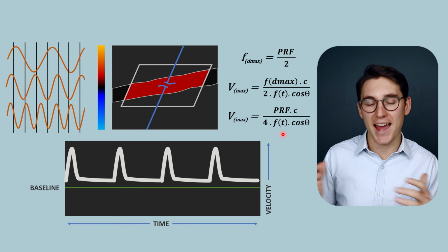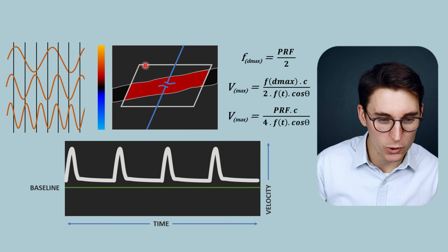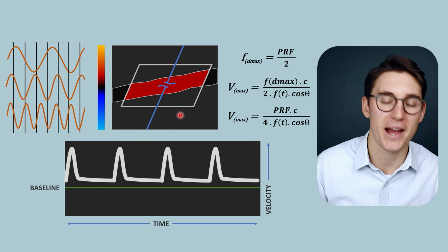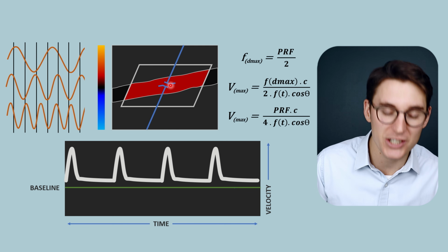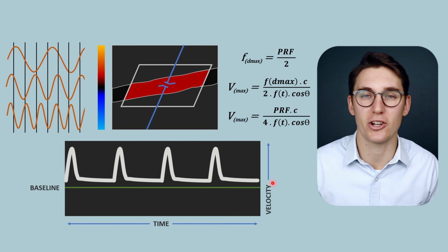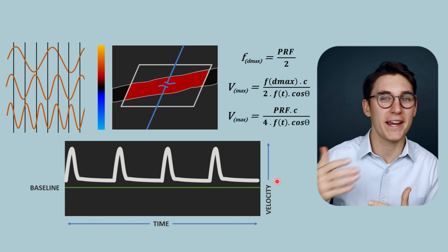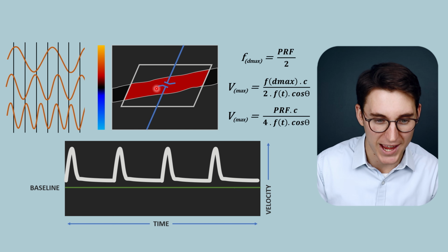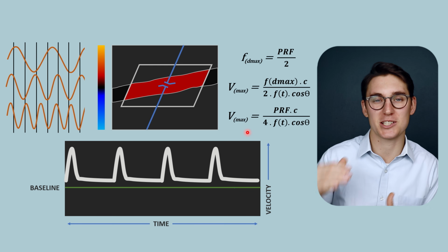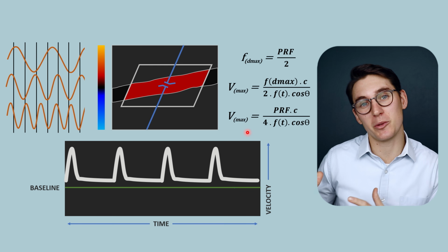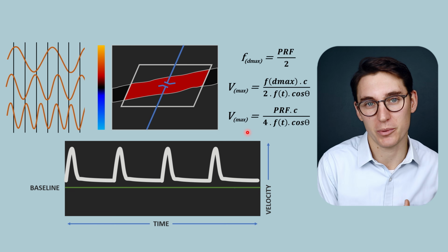Pulse wave Doppler has various advantages. We can superimpose color images over a background B mode image. We can select specific depths and specific regions on our image to measure specific velocities. But because we are waiting for those returning echoes in order to accurately plot those, we can only measure up to a certain maximum velocity.